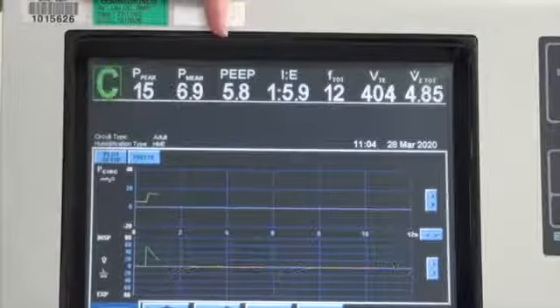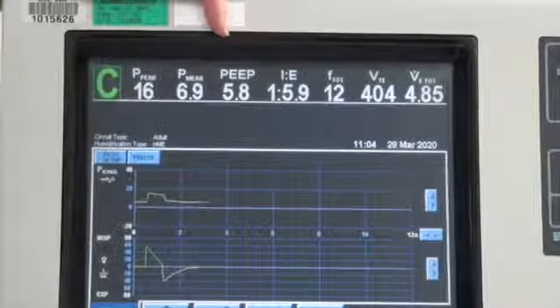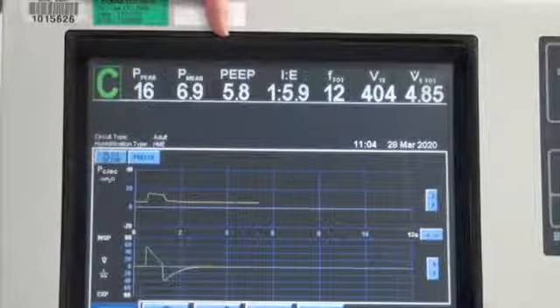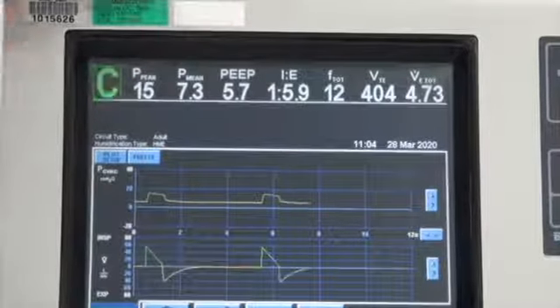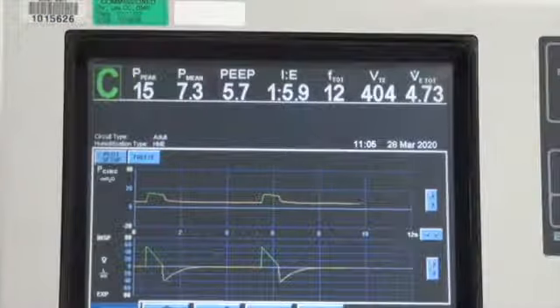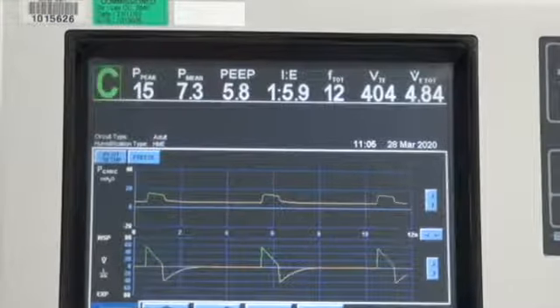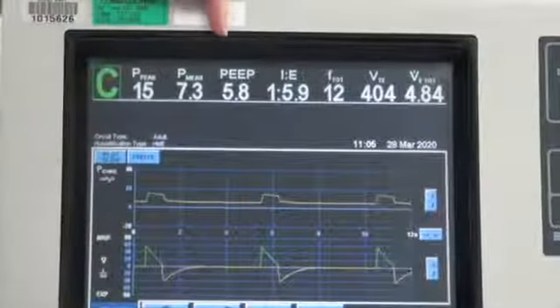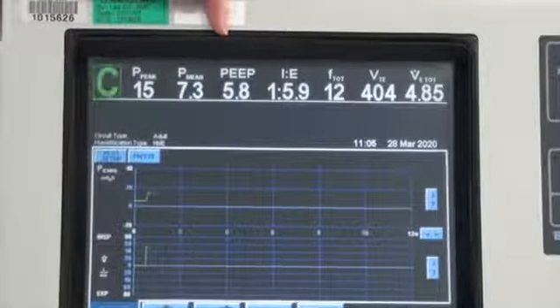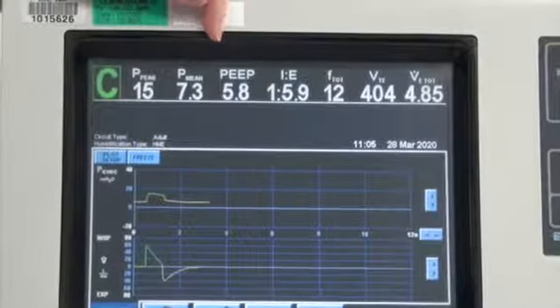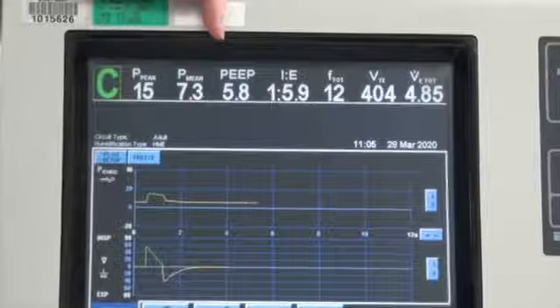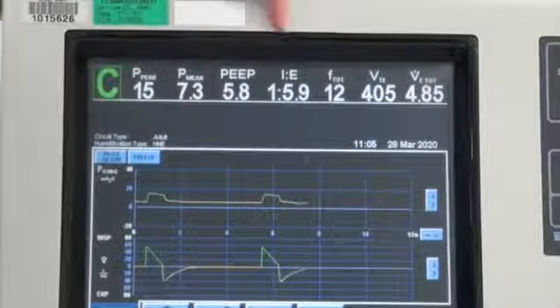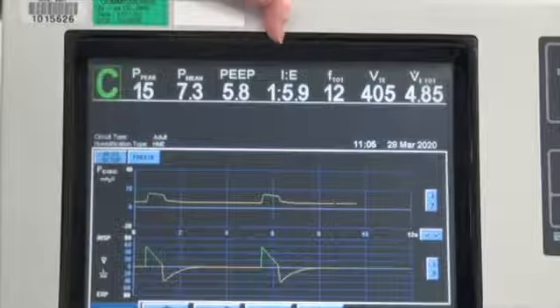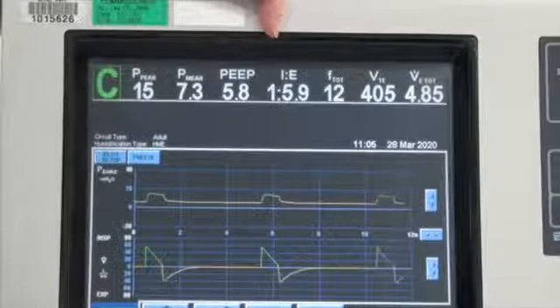The next button is the calculated or measured PEEP. Usually it's very close to the set PEEP that you have, but in certain patients with air trapping and auto PEEP, these numbers could be much higher, and that potentially can give you the warning that the patient may have auto PEEP. The next reading is actually the inspiratory to expiratory ratio.